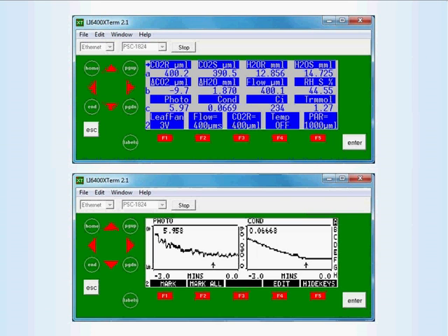The incoming and sample chamber humidities are virtually the same as in the previous slide, but the stomatal closure was arrested just by reducing the wind speed around the leaf. Reducing the fan speed increases the boundary layer thickness. The leaves of rice plants are often quite sensitive to small changes in humidity within the boundary layer.